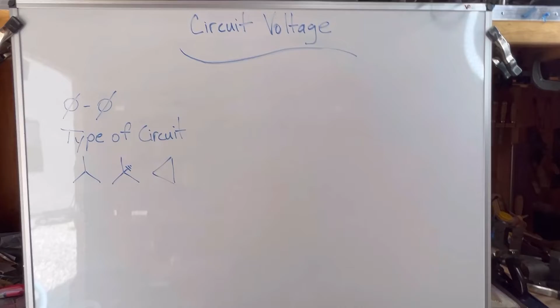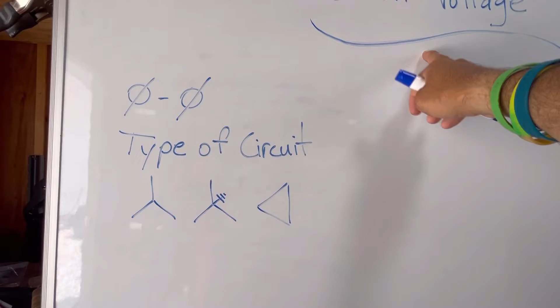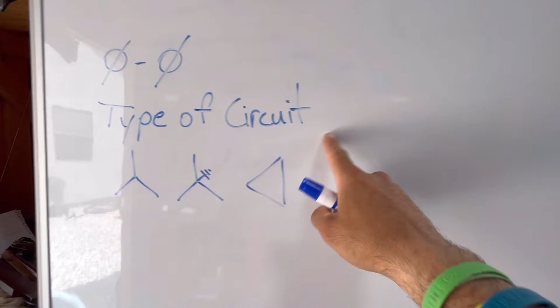All right, guys, so the first thing that we're going to talk about is circuit voltage. And what I mean by circuit voltage is the phase-to-phase potential of that circuit and the type of circuit it is, whether it be a Y, a grounded Y, or a delta. And now I'm going to break down what exactly it means to be a Y circuit and a delta circuit, and we're going to talk about where those voltages come from on that circuit. The reason we're doing that, guys, is so we can know what is available to us in terms of voltage when we go to hook up a transformer.